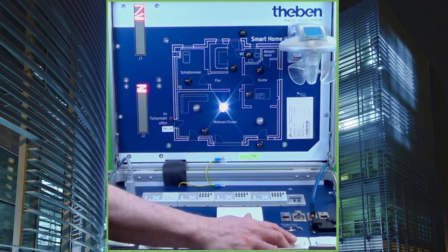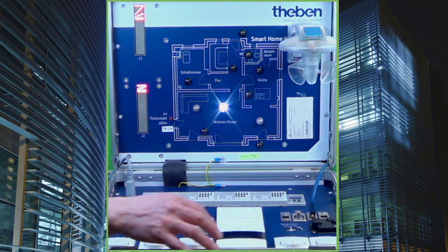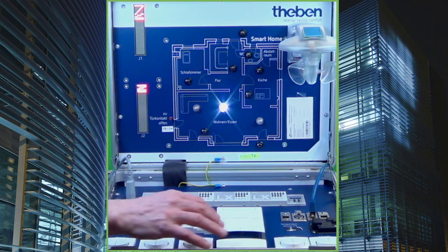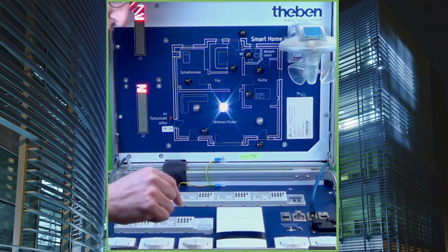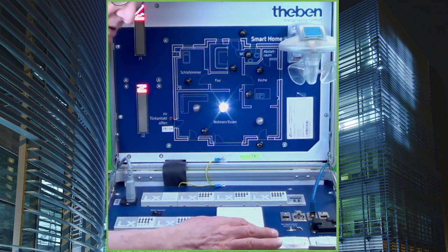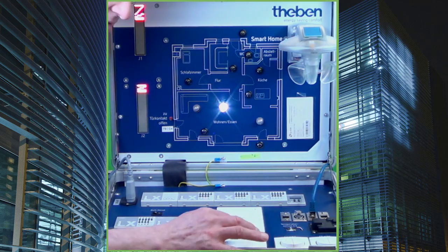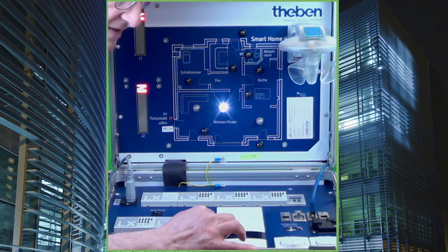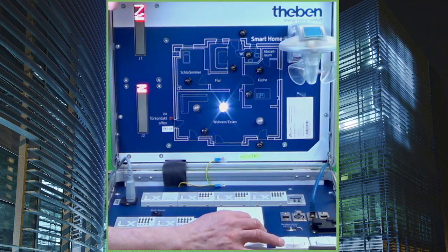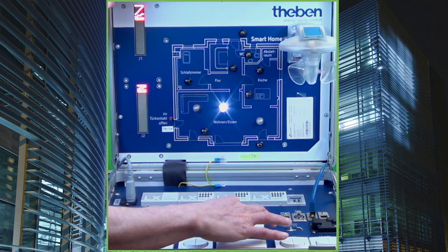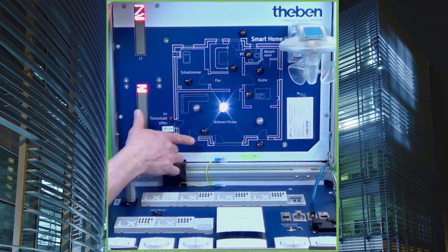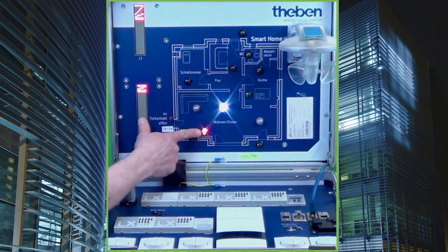The scene button I cannot show right now, because therefore I really need the scenes and LUXORplay. About the temperature right now, we have an actual temperature of about 25 degrees. The set temperature is 21 degrees, so I have to push it up to probably 26 degrees. And now, after a while, the red lamp should switch on. So also this one is working.